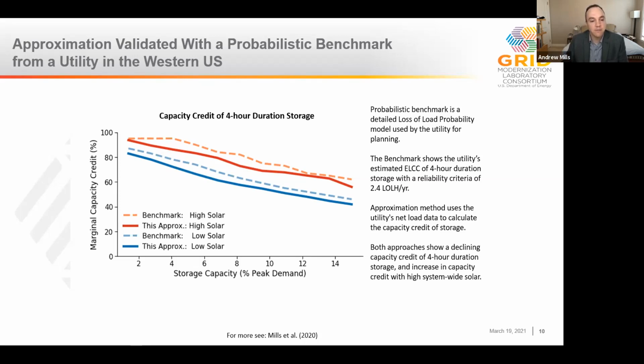We did this for different levels of 4-hour duration storage and different deployment levels, in scenarios with low and high solar. Both approaches show that the capacity credit of 4-hour storage starts near 100% of nameplate capacity but declines as more storage is added. This happens because the remaining net load peak that storage must meet gets wider as narrow peaks are clipped, meaning further reductions require longer duration storage, or a 4-hour duration storage yields a lower effective capacity credit.